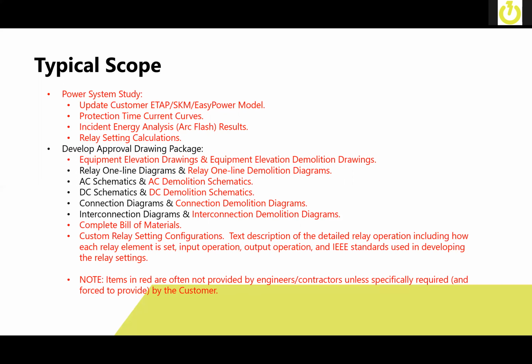The custom relay settings configuration includes a text description of the detailed relay operation, including how those relay elements are set, how all the inputs operate, how all the outputs operate, along with any and all IEEE standards that are used in developing the relay settings.